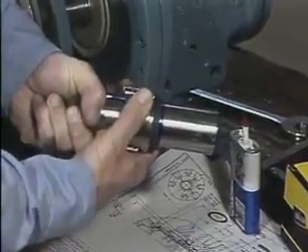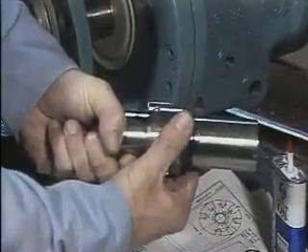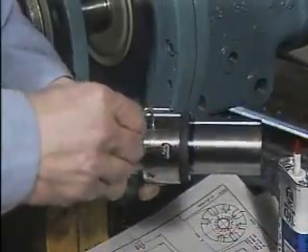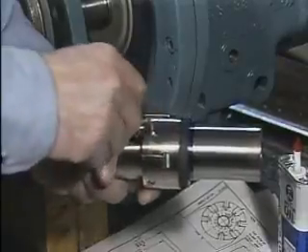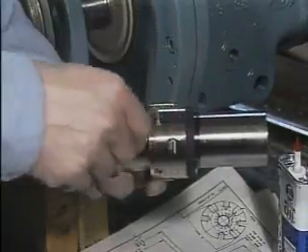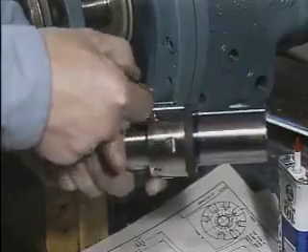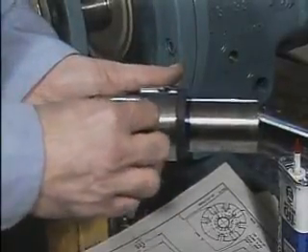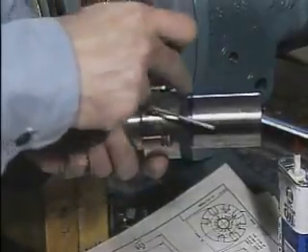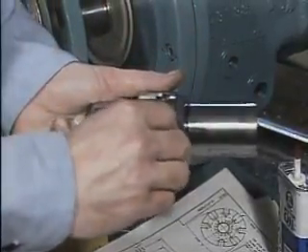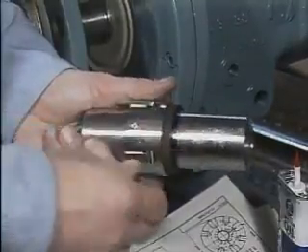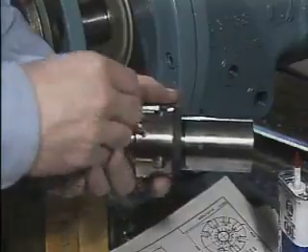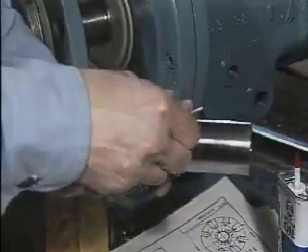The rotating element is slid onto the shaft sleeve, and the end of the rotating element collar that's opposite the seal face is aligned with the scribe mark that was made according to the location dimension. It's important to align the rotating element properly because the seal could fail prematurely if it isn't. Once the collar is positioned, the set screws on the collar are tightened just enough to hold the collar in place. If the set screws are over-tightened, the sleeve could become distorted and might not fit on the shaft properly. The screws will be tightened the rest of the way later when the sleeve is installed on the shaft.